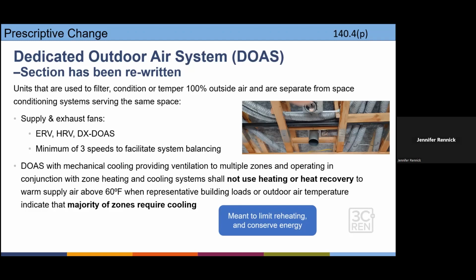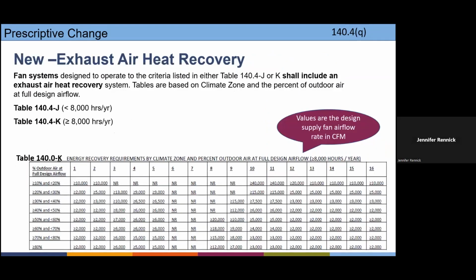But now they've said, if you're going to do that, you have to meet certain fan efficiencies with that system. This all makes a lot of sense, right? Because as our buildings are better insulated and performing better, we have smaller heating and cooling loads, but we still have the ventilation requirement. By decoupling those two, we're able to get better efficiency out of each one, depending on the different demands. And for the exhaust side on the air heat recovery systems, these new tables are included, with efficiencies spelled out per the amount of cubic feet per minute the system is moving.